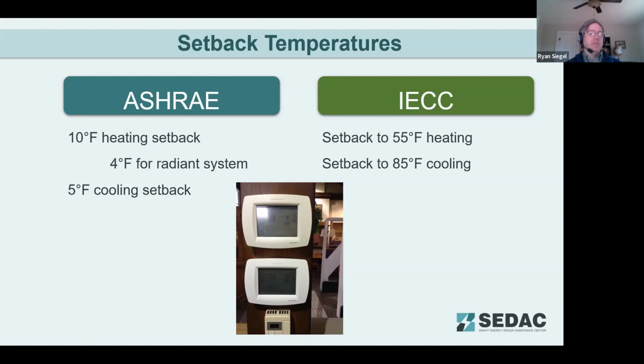ASHRAE also does have a little provision in there if you are using a radiant system to only set it back 4 degrees instead of 10 degrees. And a lot of that is because radiant systems don't respond as quickly. And as a side benefit, radiant systems oftentimes allow the systems to operate effectively, typically at a little bit of a lower set point too. So having that smaller setback from that lower set point makes a little sense.